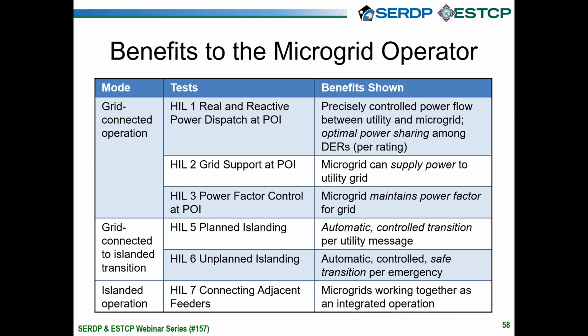In the first example, what I showed is reactive power dispatch. We have precisely controlled power flow between the utility and the microgrid, and we can also support optimal power sharing among the DERs that are in the microgrid itself. So these are following their ratings.